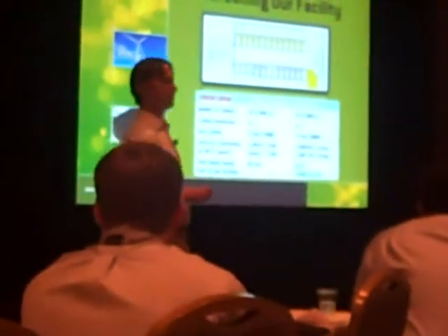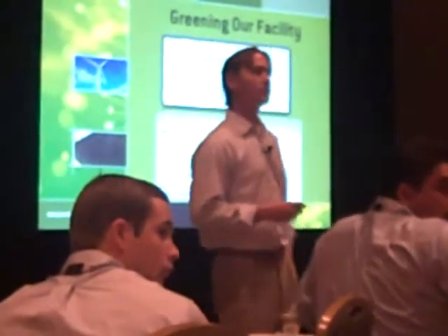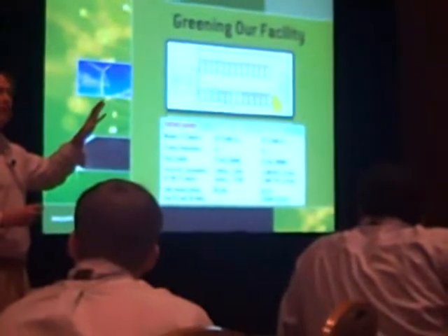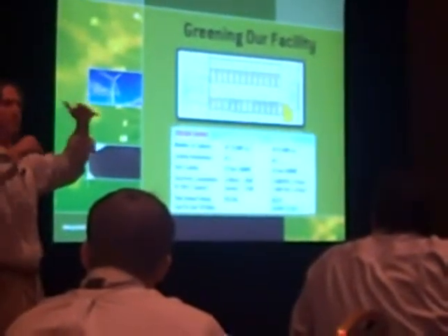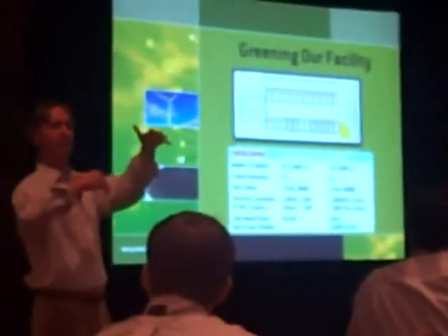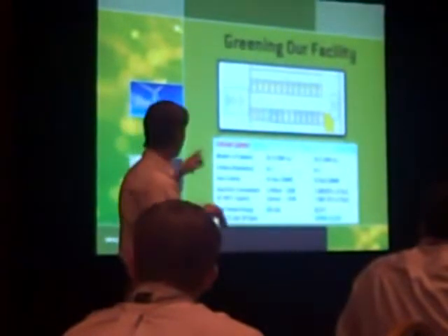Any questions on that? We'll have questions at the end as well, so feel free to ask a question. Yes. How do you control the pressure if something's out of whack? So basically, from both the supply side is a variable speed drive and the exhaust is a variable speed drive. So the difference is just in the pace at which it allows things to come in and expel. That's how we, with the combination of the servers in each row and the pace at which they're pulling air through, we're able to measure and control that pressure.